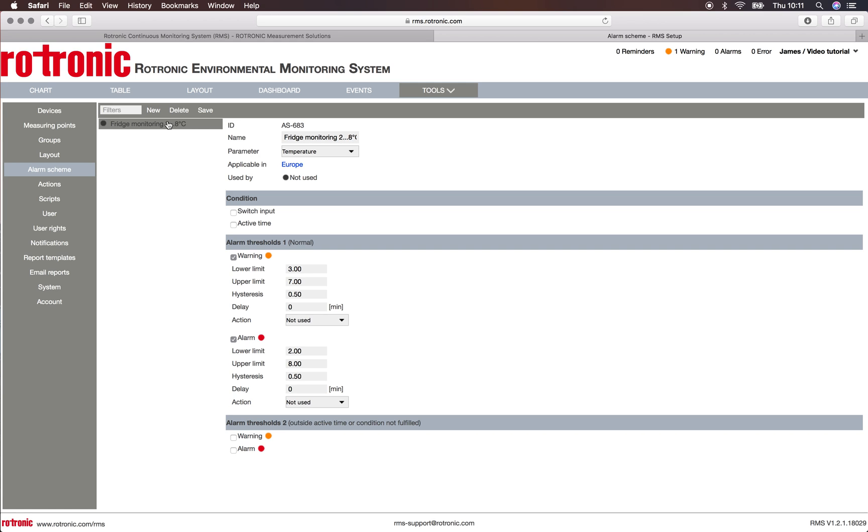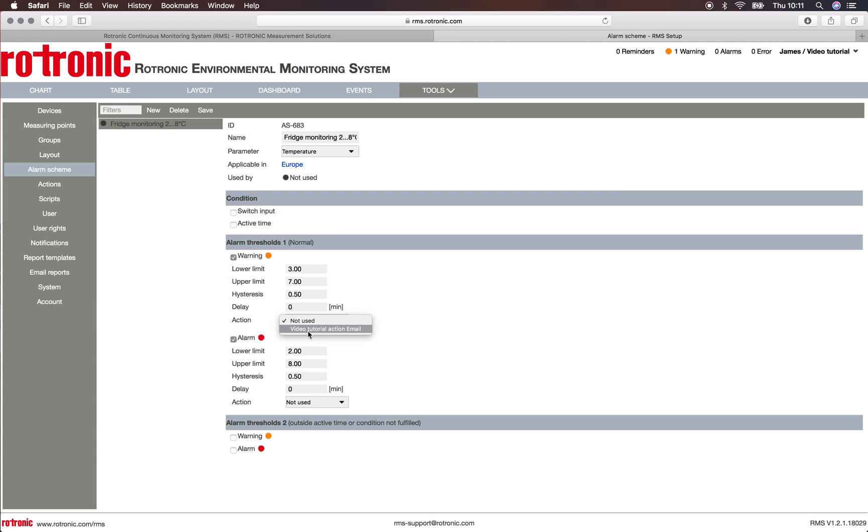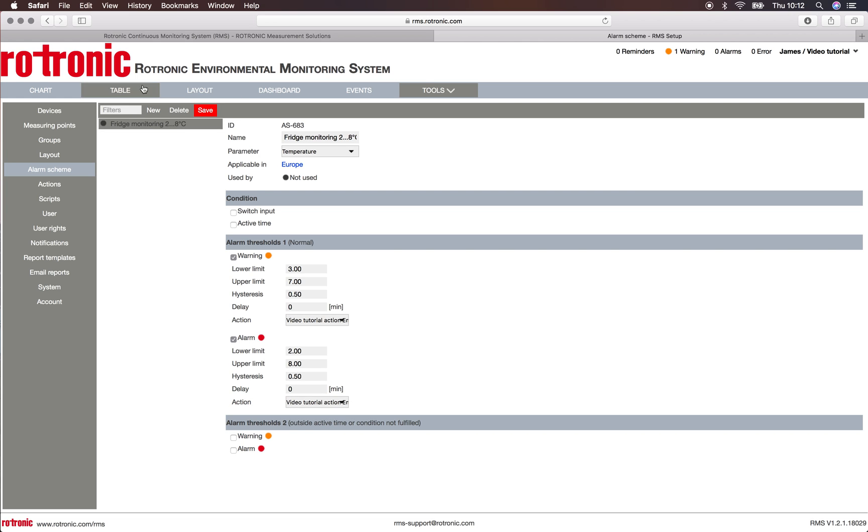We can then say as soon as for this alarm here, so fridge monitoring between two and eight degrees, as soon as there is a warning or an alarm, I can define the action. And this is video tutorial action email. I can define this for both the warning and the alarm, and click on save.